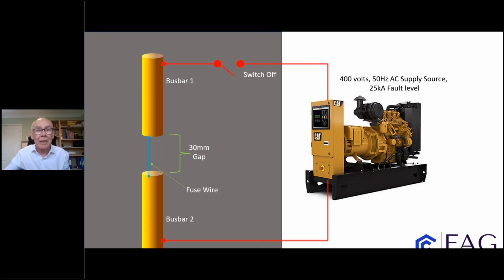Arc flash is usually caused by inadvertent contact between an energized conductor, such as a bus bar or cable, with another conductor or an earth surface. Put simply, it's insulation breakdown, and very often the insulation in question on low voltage systems is simply air. Sadly, the cause of insulation breakdown is very often human intervention.